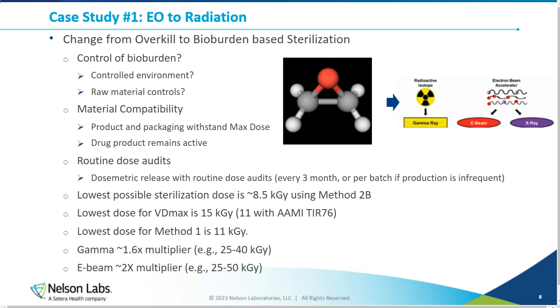All those things, controlled environment, raw materials, in order to ensure that we have a low or at least controlled bioburden. Generally speaking, the more bioburden you have, the more radiation the product is going to need in order to be considered sterile. With that, that leads into our material compatibility. Product and packaging need to be able to withstand that maximum dose. Radiation is going to have a different effect on the product and its packaging system than ethylene oxide. Ethylene oxide has considerations that are going to be different than radiation as well. So we need to make sure that we're accounting for those materials and their compatibility.